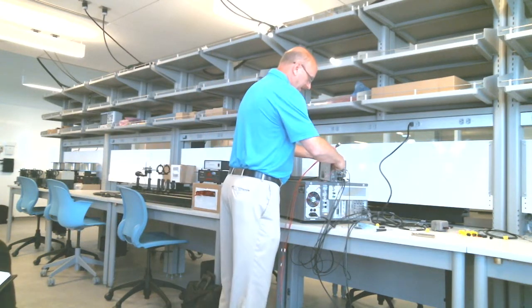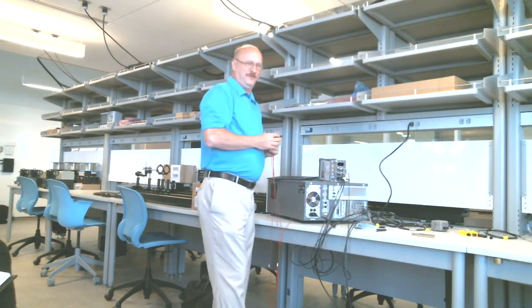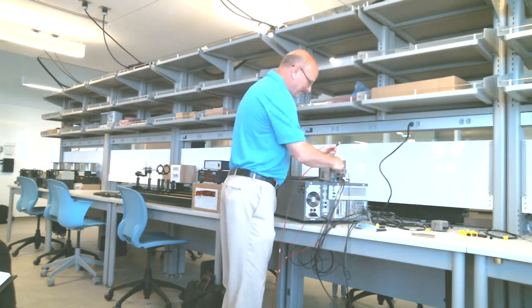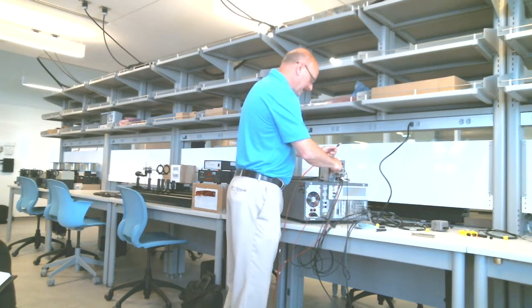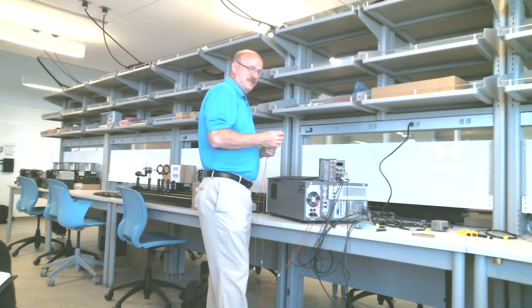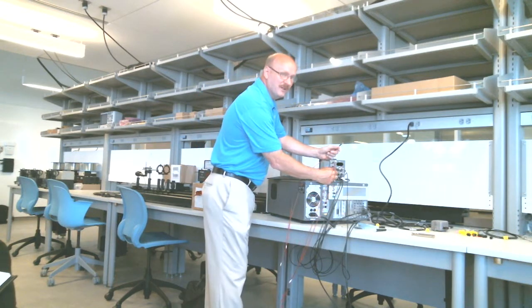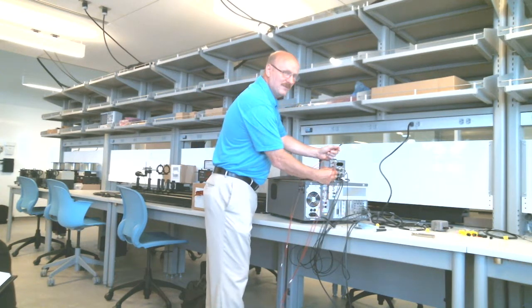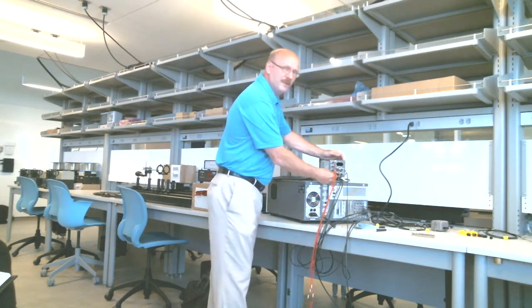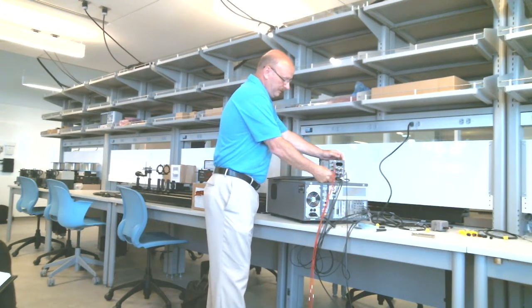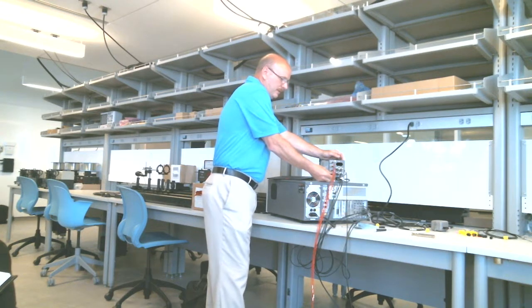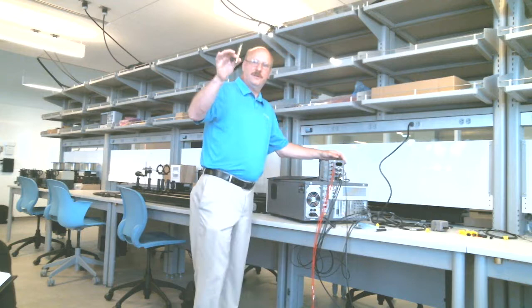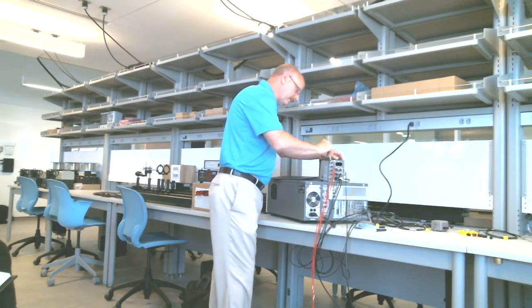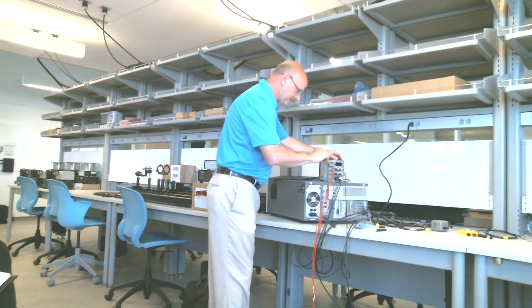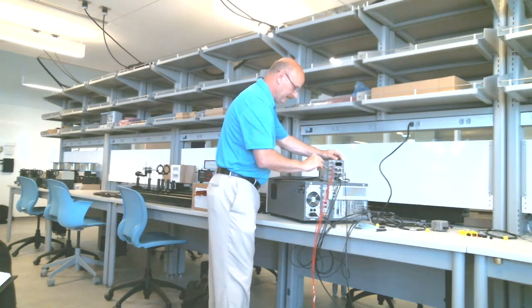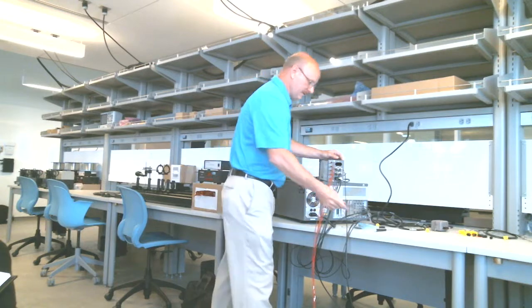So the length of these cables is programmed into the system. You can change it, but it's defaulted to 1.5 meters, which is what these are. So you can change the length from the settings. You can change them, yes. You can compensate. There's what's called compensation. You can compensate for length, you can compensate for shorts, you can compensate for opens, you can compensate for loads. Okay, but these cables work very well, and we give you this. You use this because that's important. It's a torque wrench. If you don't torque these right, you may not get good measurements at high frequencies.